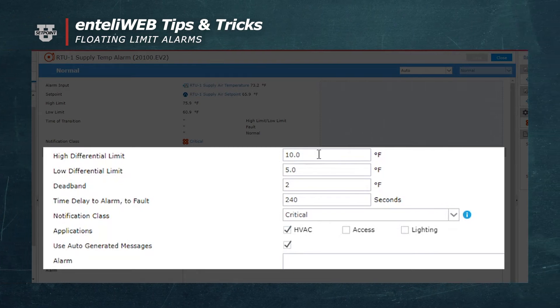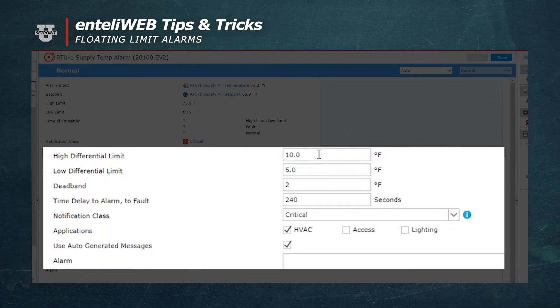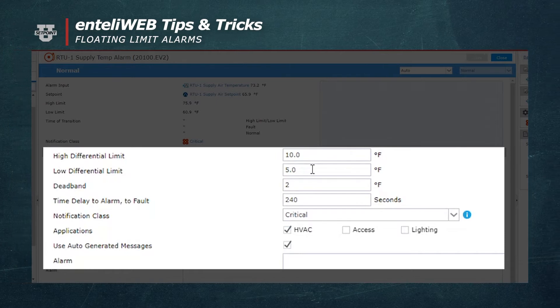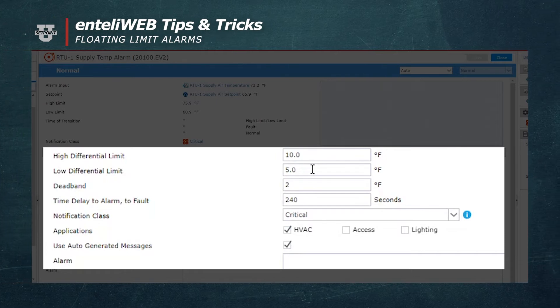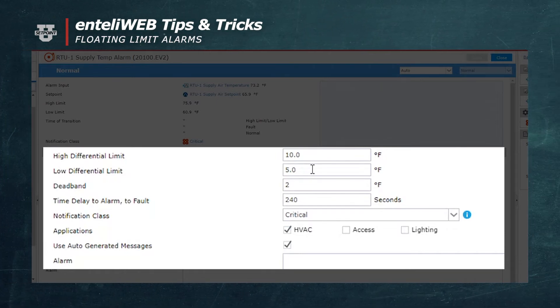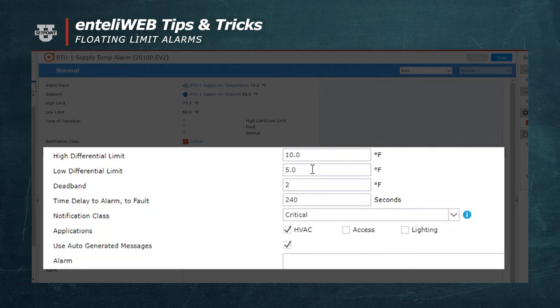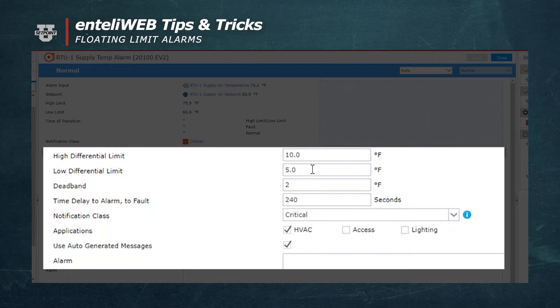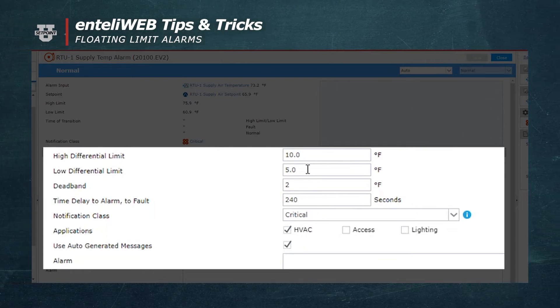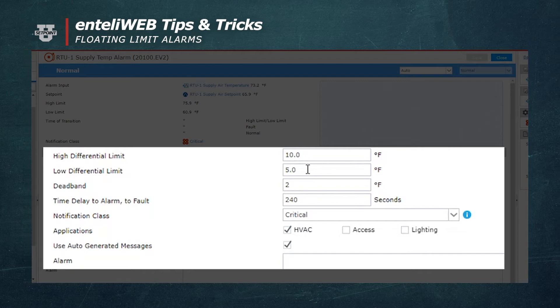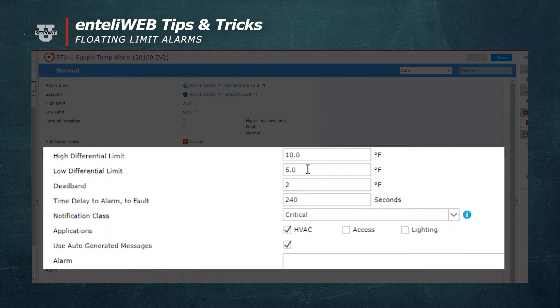The low differential is for the low side of setpoint. So if it's 5 degrees below setpoint, you would get an alarm. So if the supply air temperature was 5 degrees below setpoint, you would get an alarm.